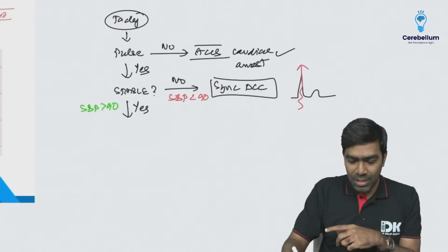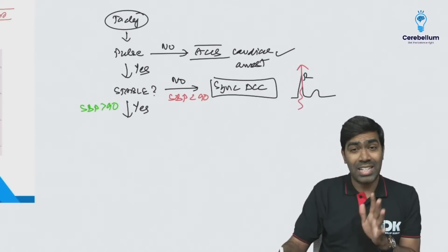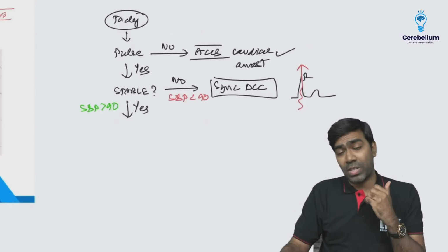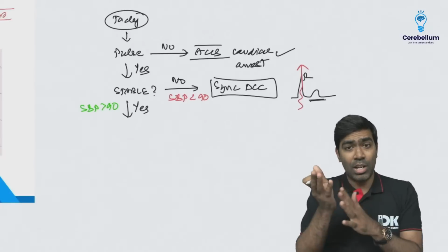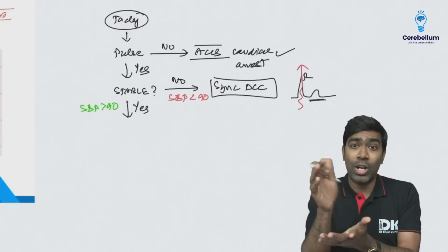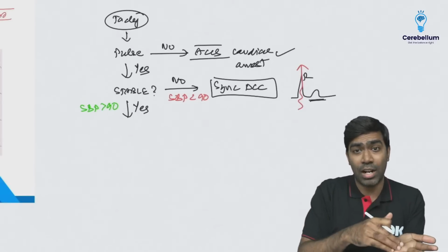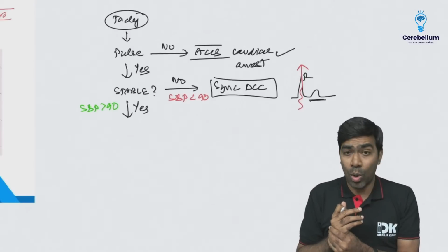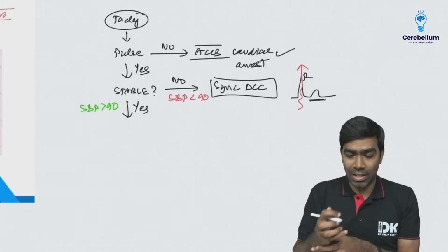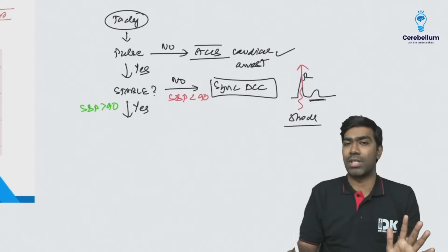Okay, it's going to time the shock in such a way at the peak of the R wave. That is very important because in certain tachyarrhythmias, if you by mistake shock during the T wave, especially during the beginning of the T wave, that will result in something called R on T phenomenon, and that can result in degeneration of the pre-existing tachycardia to worse tachyarrhythmias like VF and torsades. So that's why you should avoid R on T phenomenon. That's the reason why the shock should always fall on the peak of the R wave in most circumstances.